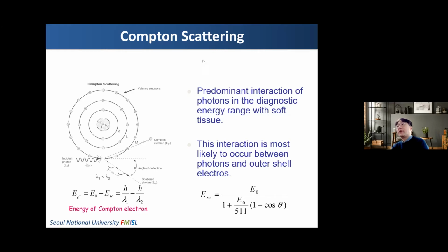So Compton scattering is quite important. What will happen if we do not reject such Compton scattered photons? If a photon is scattered, its angle is quite random, so it is hard to say where its origin of emission was. So these Compton scattered photons contribute to the images as background noise. That is why we should remove these Compton scattered photons based on the energy window.